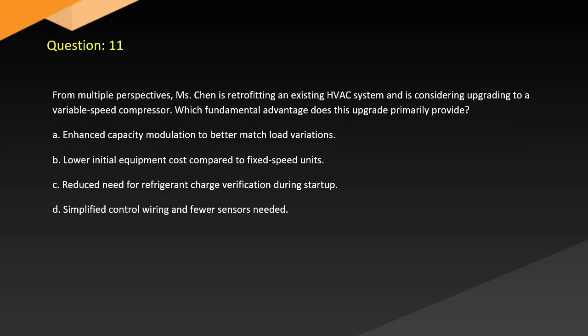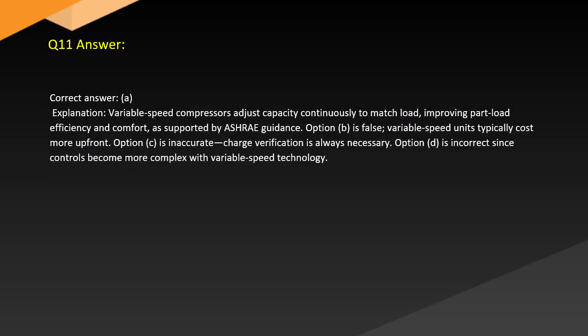Question 11. From multiple perspectives, Ms. Chen is retrofitting an existing HVAC system and is considering upgrading to a variable speed compressor. Which fundamental advantage does this upgrade primarily provide? A. Enhanced capacity modulation to better match load variations. B. Lower initial equipment cost compared to fixed speed units. C. Reduced need for refrigerant charge verification during startup. D. Simplified control wiring and fewer sensors needed.